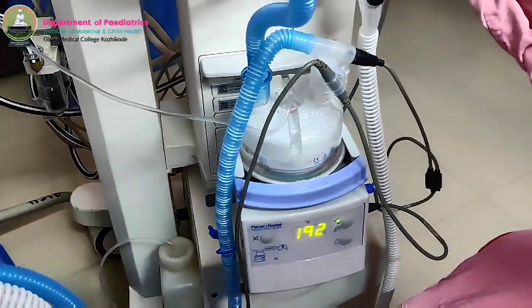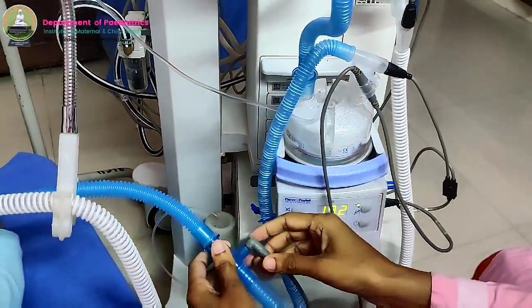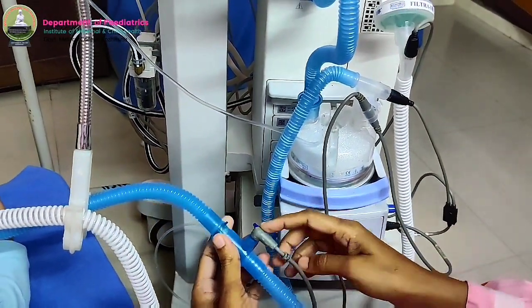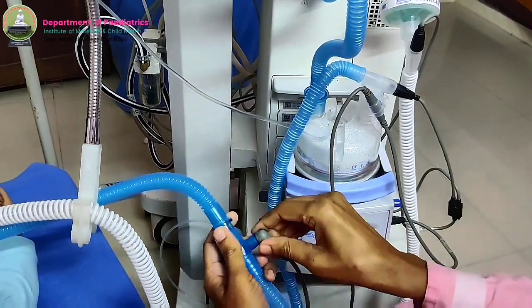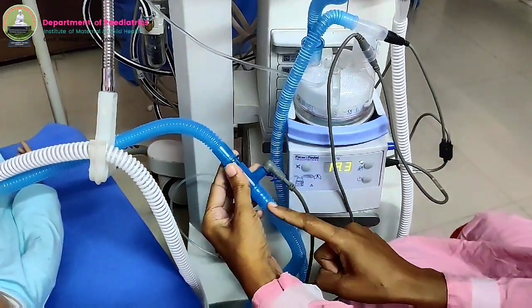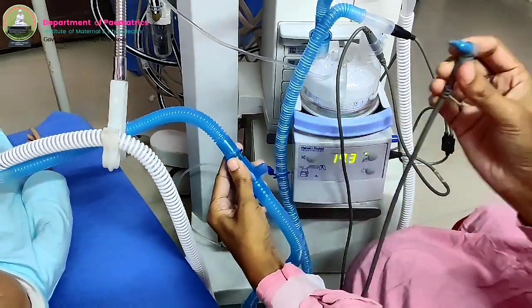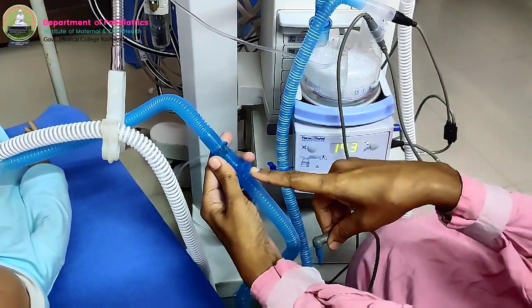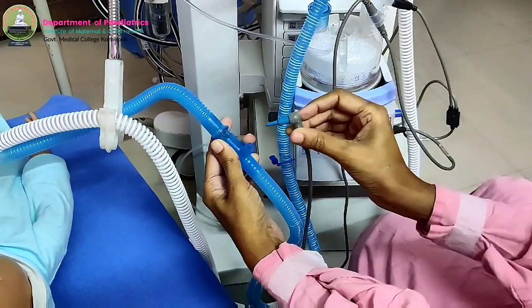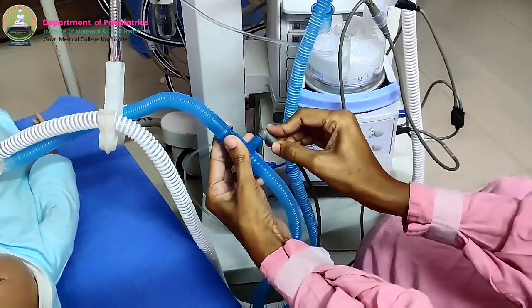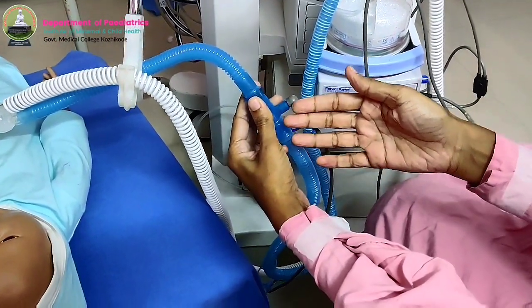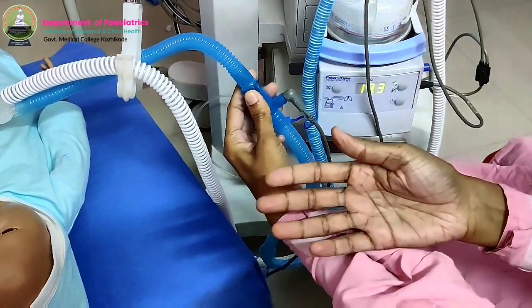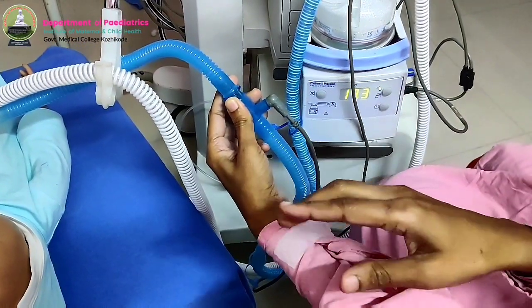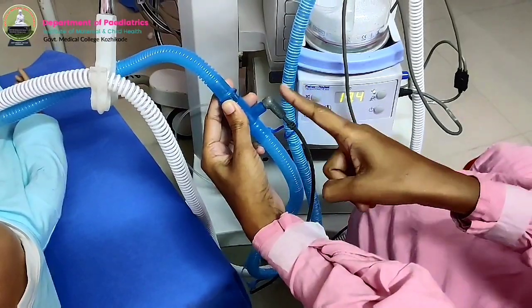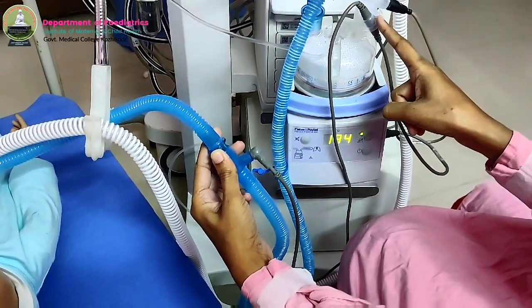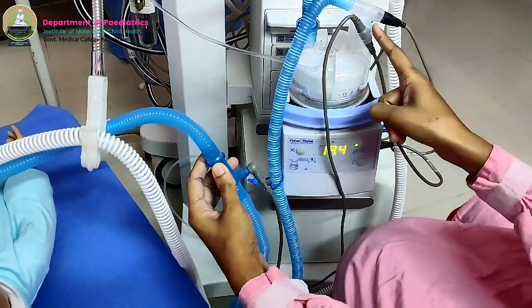Another important point is when we connect this sensor, always make sure that we are measuring temperature of the air. So this sensor is in connection with the lumen of the circuit. Any loose contact with here will result in escape of gas from the circuit and the tidal volume delivered will be very low and the patient will become hypoxic. So these 2 points are very important. So these 2 points should be properly fixed.